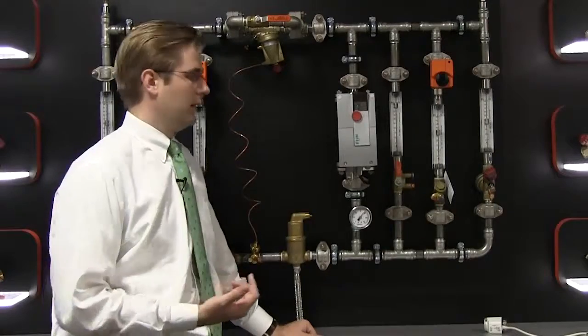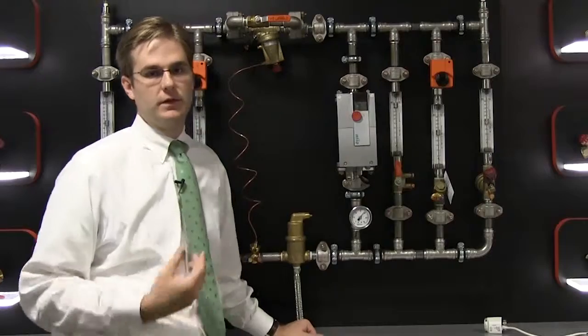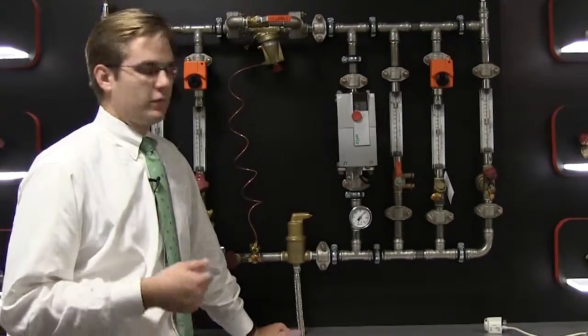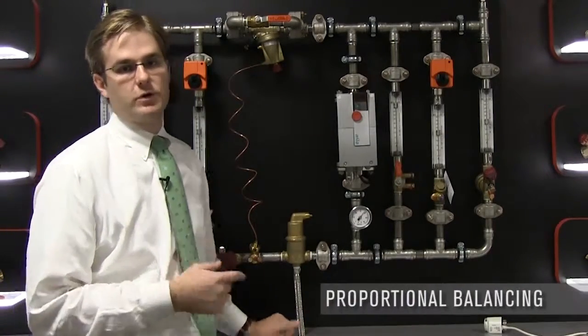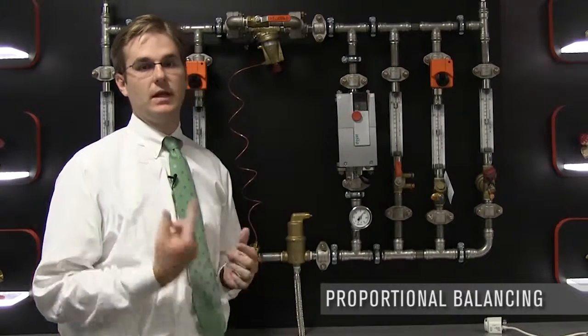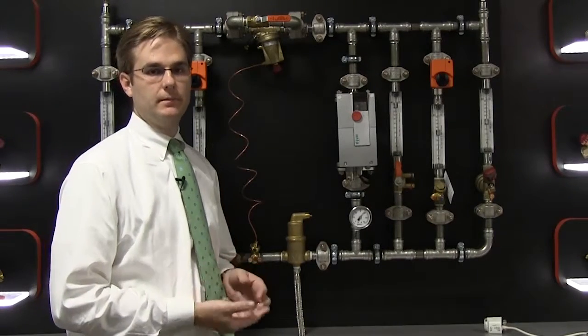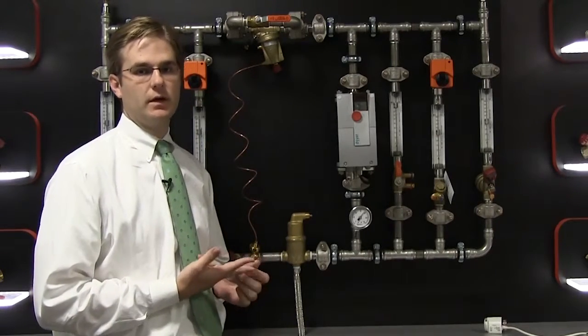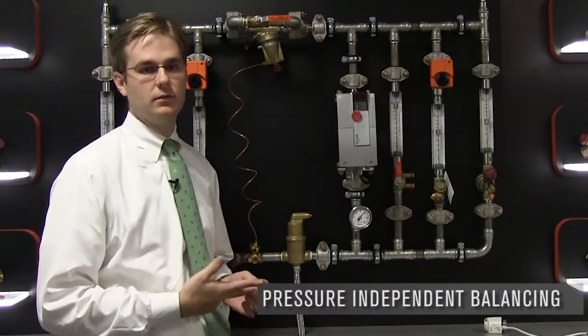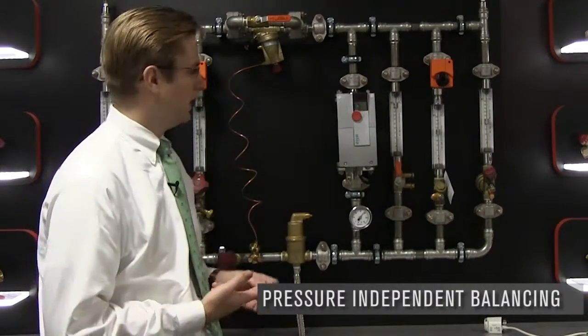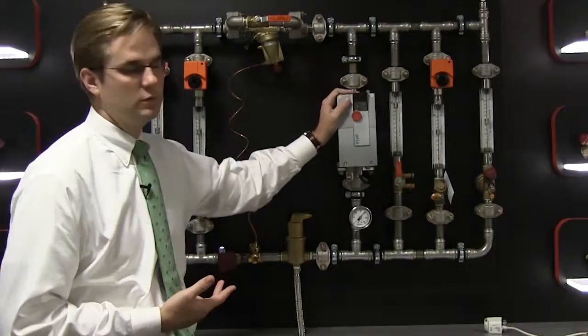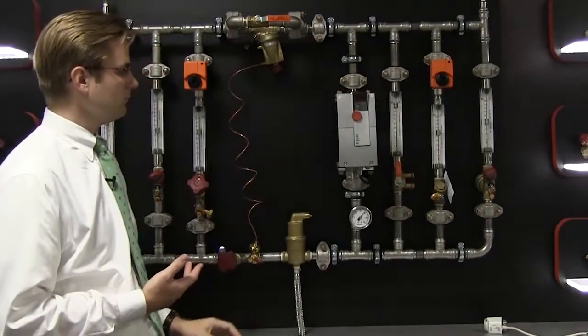Today we're going to be talking about two types of balancing at our new balancing wall here at Victaulic headquarters. The first type of balancing we're going to be talking about is proportional balancing, which means getting enough flow at each terminal unit. The second type of balancing we're going to be talking about is pressure-independent balancing, or energy-efficient balancing. And to do that, I'm going to use our new balancing flow loop.